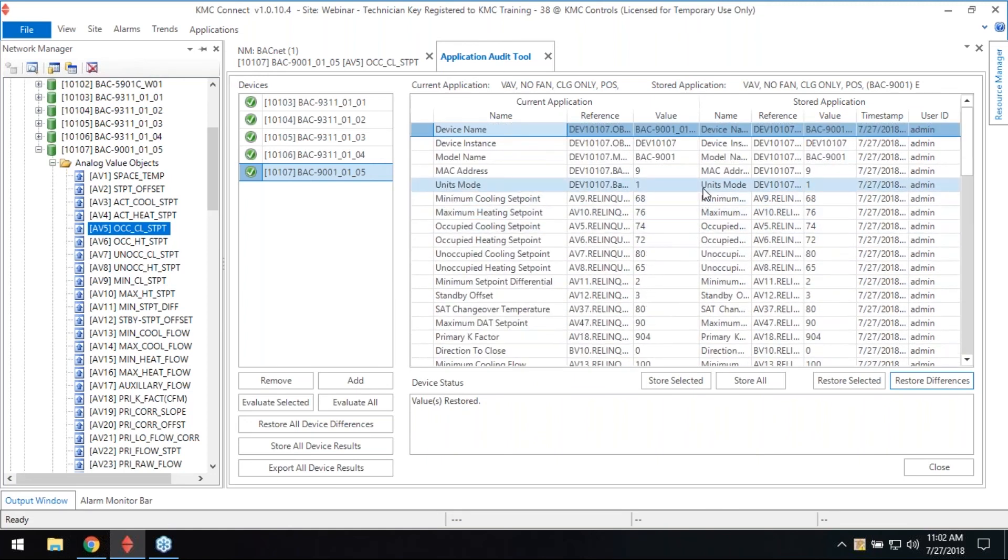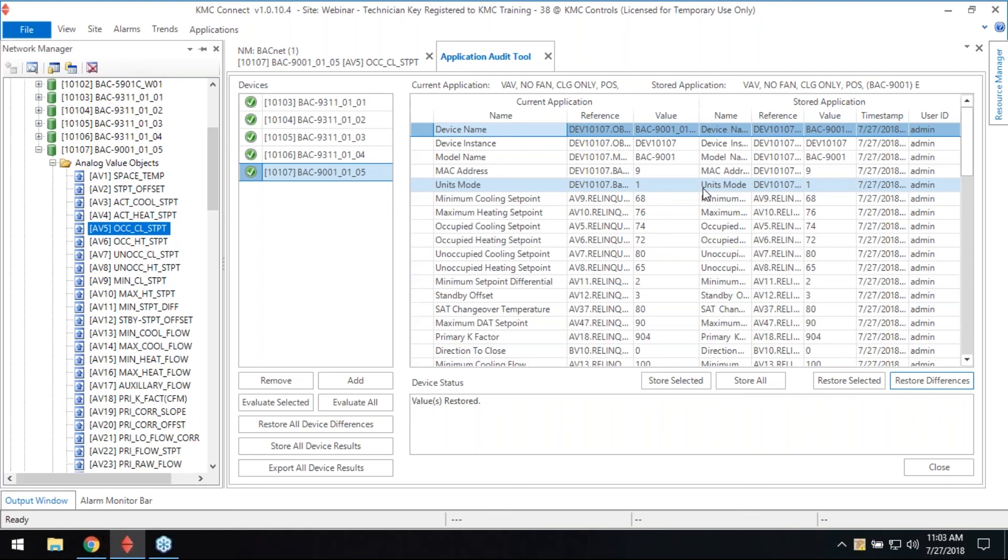Now this doesn't, like if somebody went in and changed the code, reprogrammed it, it won't catch that. So the sequence of operation, we really can't evaluate, but we can evaluate any set points or any configuration points that have been changed. The reheat type, the fan type, any configuration point. So that's a really cool, powerful tool that I think is not getting used to its potential. That should really be part of your routine. After deployment, you do an audit. That'll give you a record of all the configuration and then evaluate the network, everything on the network really quick to give you some ways to troubleshoot your settings.